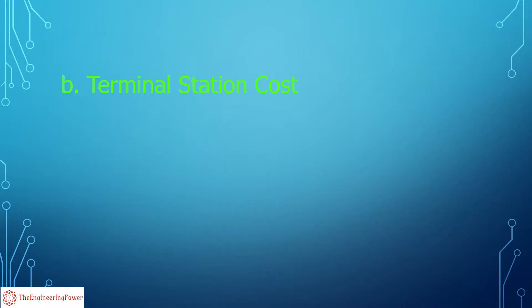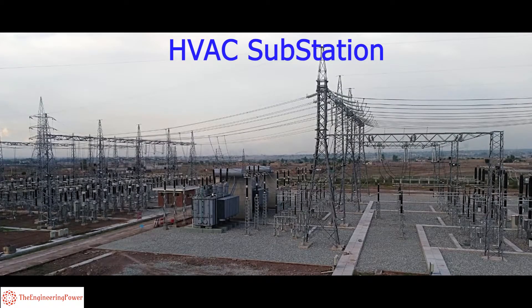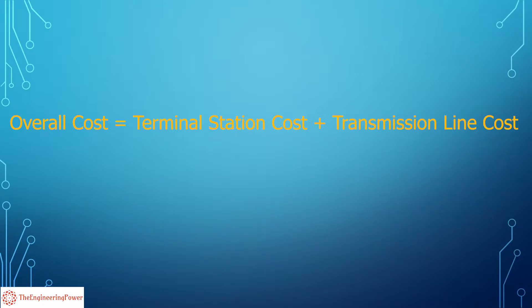Terminal converter stations in HVDC are much more expensive than the substations used in HVAC system. The overall cost of transmission is based on the terminal station cost and transmission line cost. The terminal station cost is normally fixed whereas the transmission line cost increases with the distance. So we can conclude that overall cost of transmission increases with the distance.